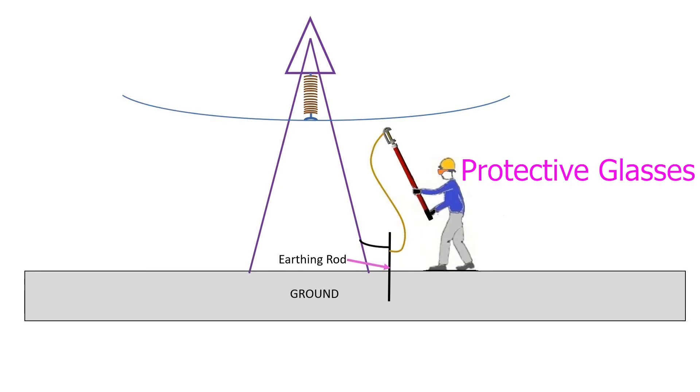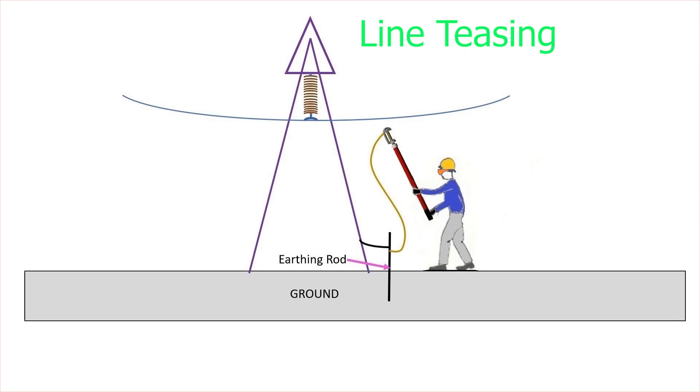Before applying PTG, line teasing must be carried out. Line teasing is basically the hearing of a buzzing sound when the ground stick's metallic head is brought near to the energized line.